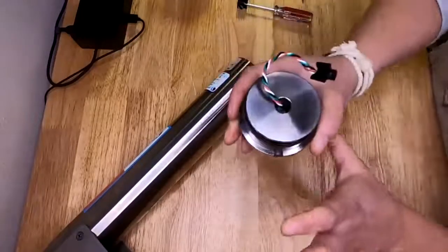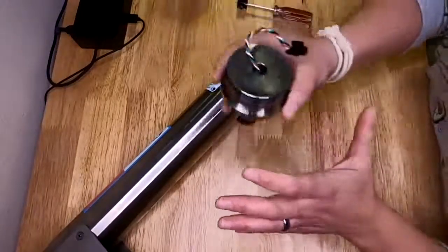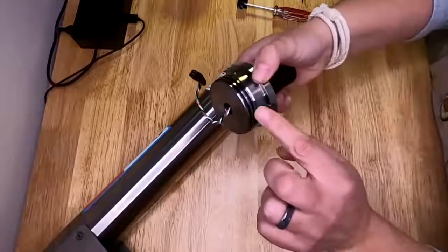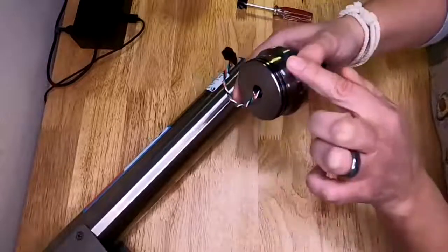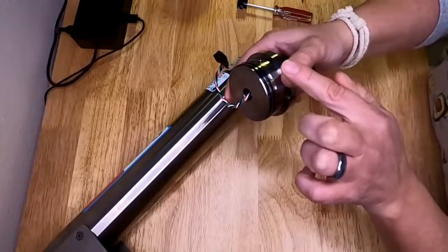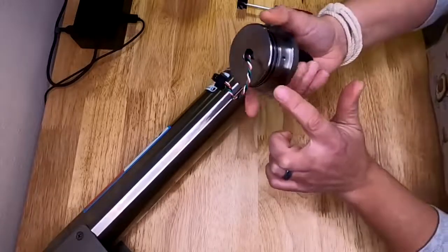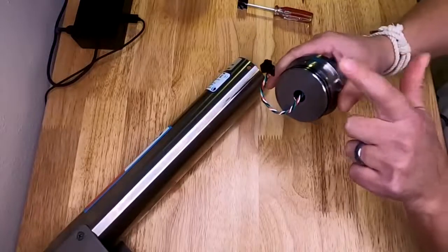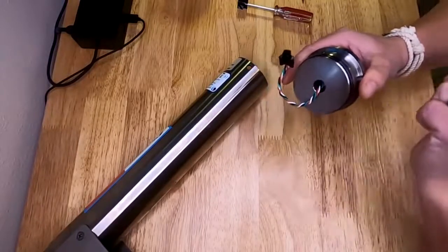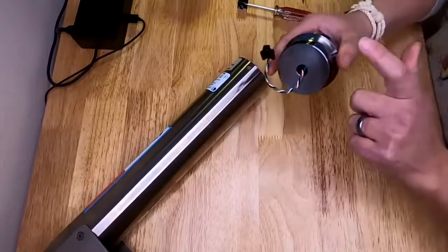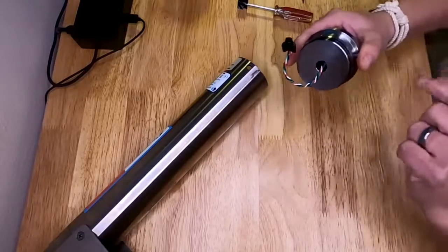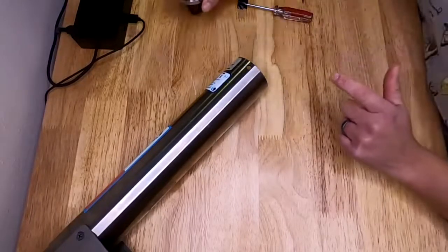All right, so I'll put this on the side. Make sure you put this in a clean place. You see these O-rings here. This is actually your seal for not letting water into your instrument, so you want to make sure that you keep this nice and clean. This morning I did this after not having enough coffee, and I dropped it on my carpet. And I did have to clean it because I have a cat, and there was a lot of cat hair on that. I hope you don't have many cats in your lab either.